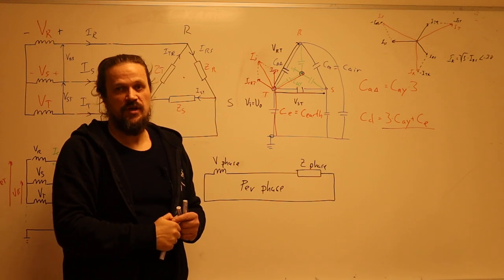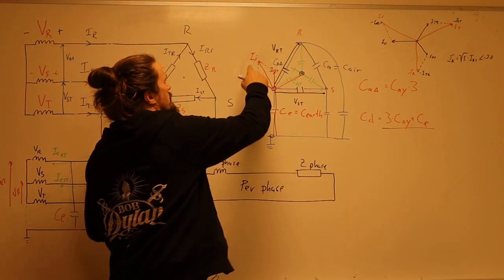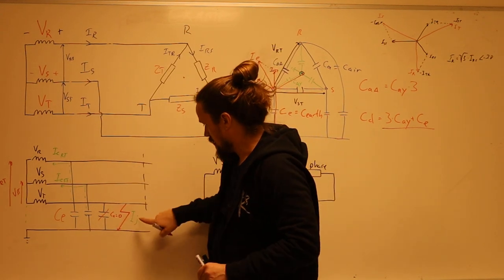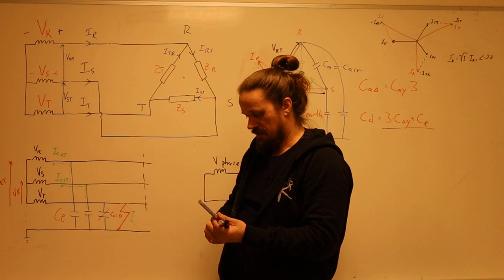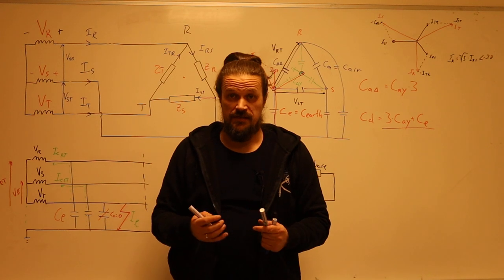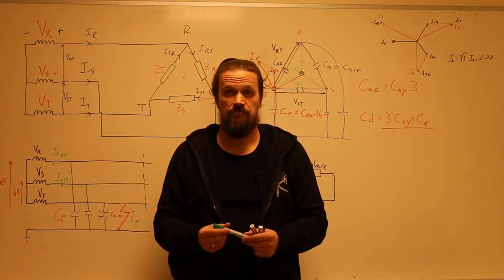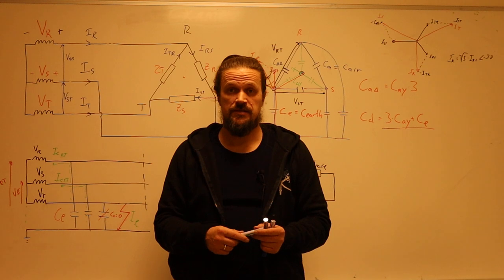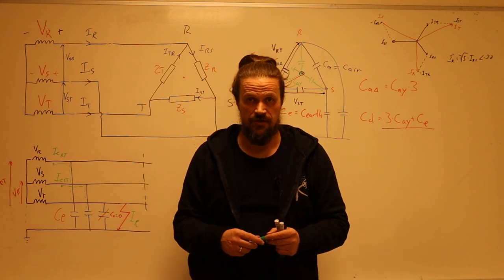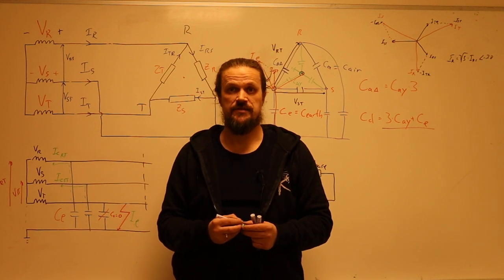The sums of those two capacitance currents will then give you the ij which in English will be ie. That's the current to earth, the one that we are computing here, ie that goes to earth. That's very useful information to know when you are managing a system and when you need to be aware of the potential earth faults and line to earth currents in a three-phase system.